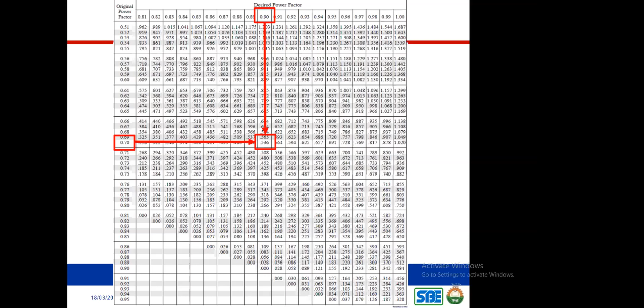Now, this is what we have at present before we begin our correction. Looking at this triangle, you have 2000 kilowatts as your true load. We don't care about the kVA. What we care about is the kVAR, because we want to reduce that inductance, that wastage. We want to bring the power factor up from 70 to 90. We have checked our table factor, and it is 0.536. If you multiply 0.536 by the true power of 2000 kilowatts, you arrive at 1072 kVAR. So that is the capacitance that you need to improve power factor from 0.7 to 0.9.